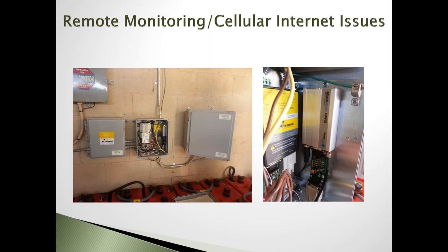Unique here is how the building works. We wanted remote monitoring to figure out how the system was working. Since we have both generation and power consumption, we had to have two different monitors — one monitoring what the building is using, and one monitoring what the solar system is generating at any given time — so we could see if there were issues with one or the other. That worked good for several years.